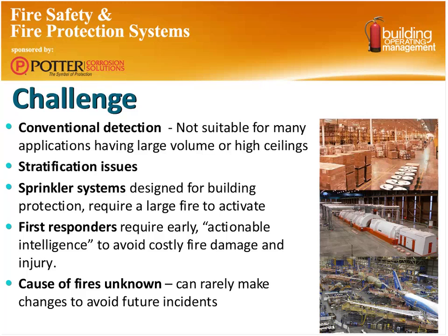So conventional detection just doesn't work too well in areas with really high ceilings. We have this thing called stratification. Smoke gets cold, quits rising up. It takes a lot of smoke to let it go up into a very high bay because of that difference in temperature. And when it does stratify, it never gets up to the detectors that are way up at a 50-foot ceiling, say as in an atrium, hotel atrium, or a school atrium, or a typical assembly facility like a soccer stadium or basketball arena.